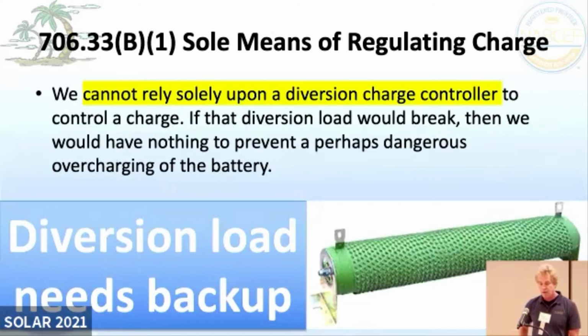There's also something called a diversion charge controller. Let's say you're off grid, it's a sunny day, you're not home, and your battery's fully charged, or you're just slow charging your battery because it's called an absorption charge. You don't always give it all you've got. So you have this extra power that you could either throw away, or sometimes people will use a dump load, something that just heats up, or they'll pump water with it, or do something useful with it. That would be a diversion load. Some people even consider it a diversion load when you're connected to the grid and you start feeding power to the grid after your battery's full.